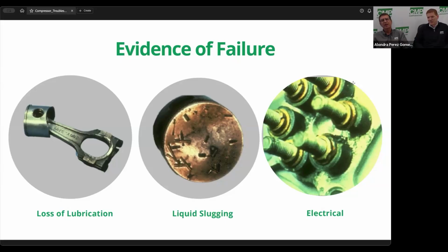It happens every time on startup. When the compressor comes on, if you want to slug the compressor, you're not going to slug it after it's been running for 5 or 10 minutes or longer. But when it's off and it's off cycle, that's when your liquid's going to come back all at once. And if the power shuts off and you have 10 or 15 pounds of refrigerant hanging out in the evaporator, and it starts moving toward the compressor, it's going to get it on startup. So liquid slugging happens on startup.